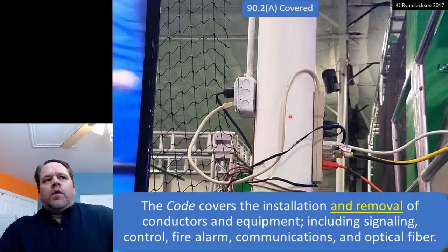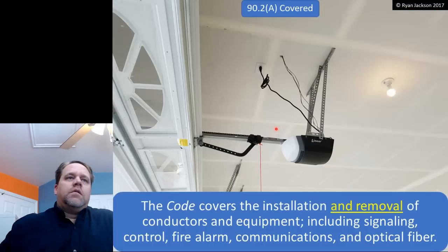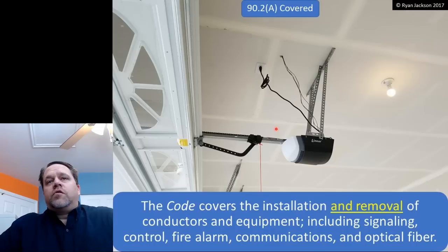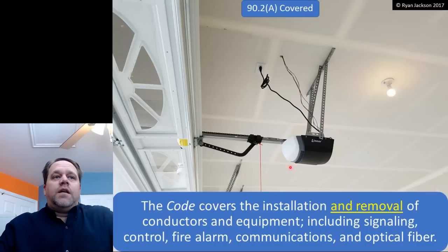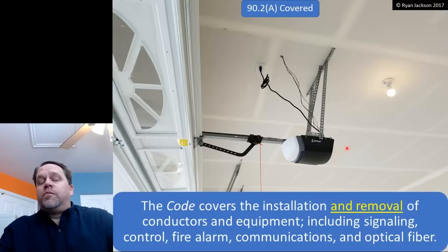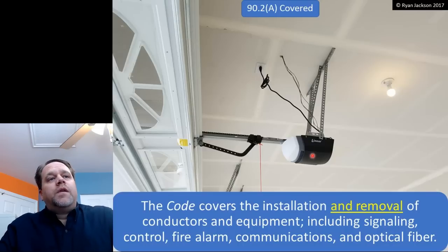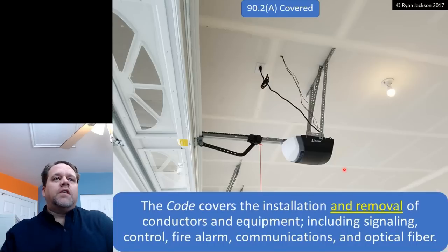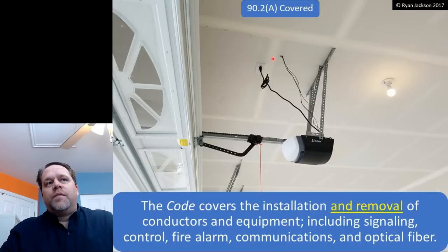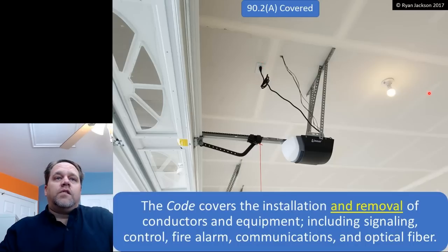So in this photograph, I would say that the code probably ends at the receptacle. But that's not always the case. Here we have some installed electrical equipment, this garage door opener. That cord is regulated by the NEC because this is an electrical installation. That is installed electrical equipment. To be more specific, that's an appliance, Article 422. So this cord is regulated by the NEC, and it has to comply because that's part of an electrical installation. So the code doesn't necessarily end at the receptacle. Sometimes it does, but it doesn't always.